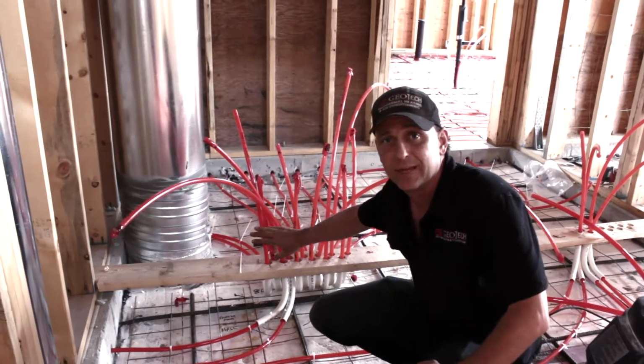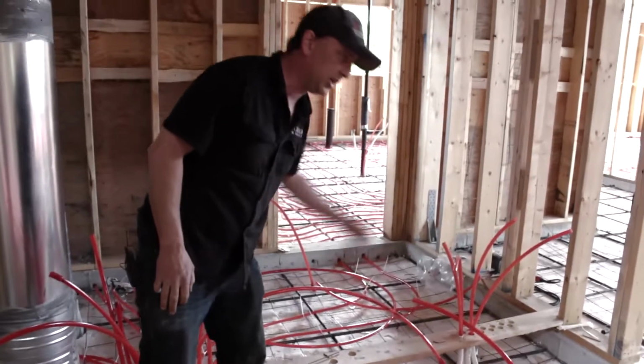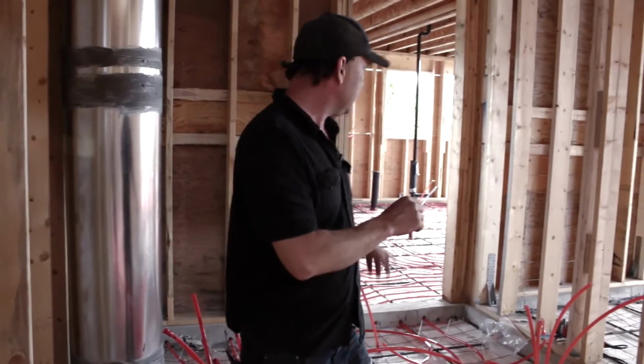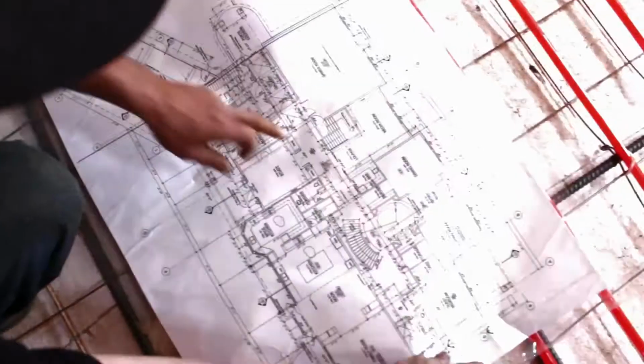We've got the manifolds, two in this case, one on this side, one on the far side. Our main lines to supply and return are going to be brought up in the middle, switched to each manifold. All our zones, again, are brought back to each manifold. Each manifold has a flow meter and also has what's called an actuator. The actuator will open and close as the thermostat asks for it, allowing the water into the floor to heat the room. So on that manifold, you'll have an actuator and a flow meter, so we can guarantee the flow rate through each one of those zones or circuits of water, so we can guarantee that there's a proper amount of BTUs, or proper amount of heat, delivered to each room.